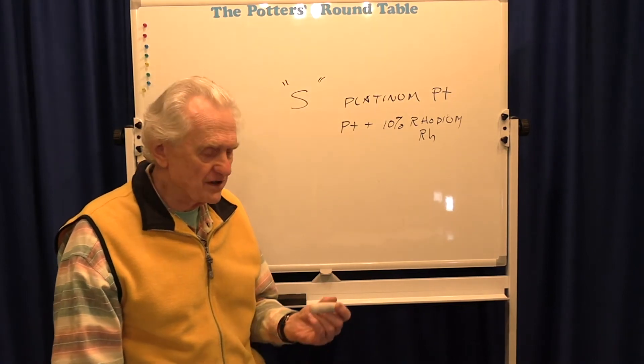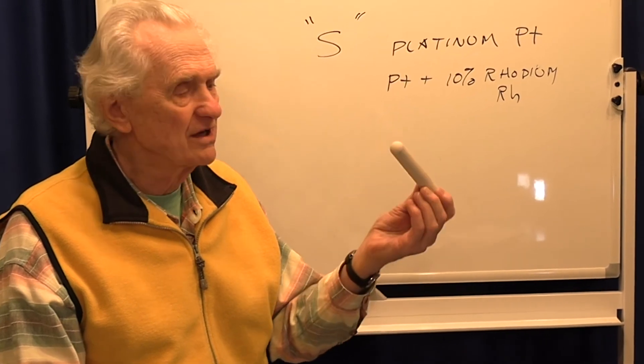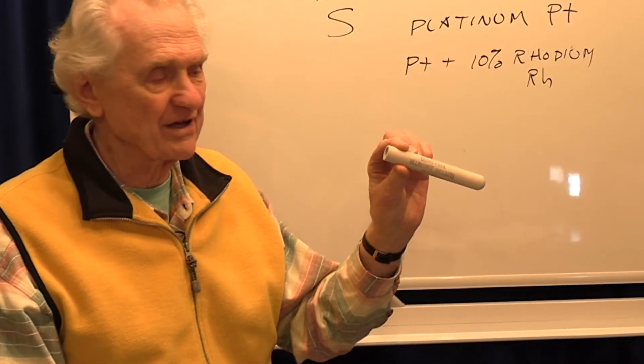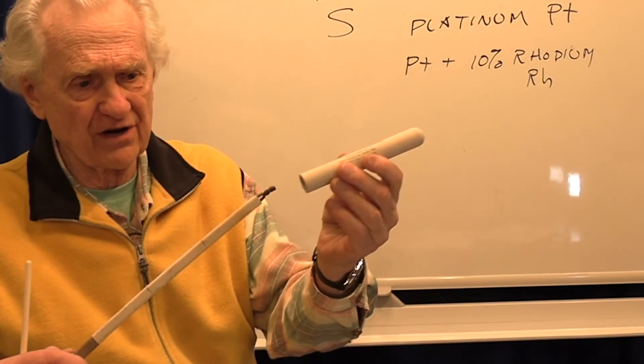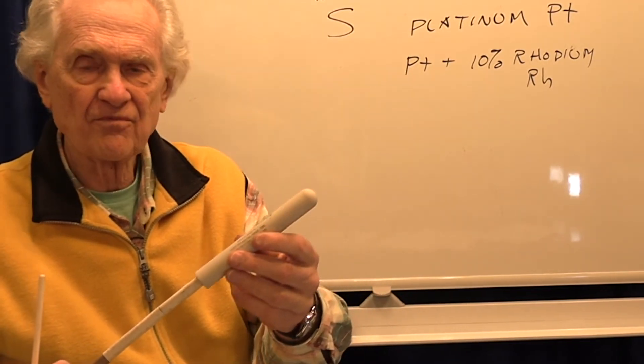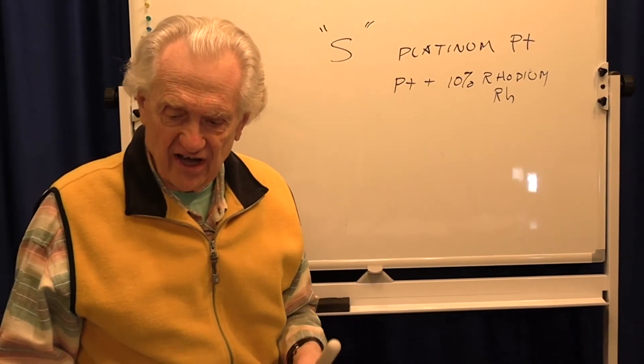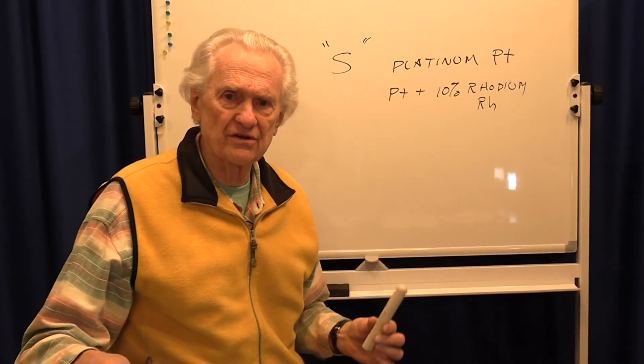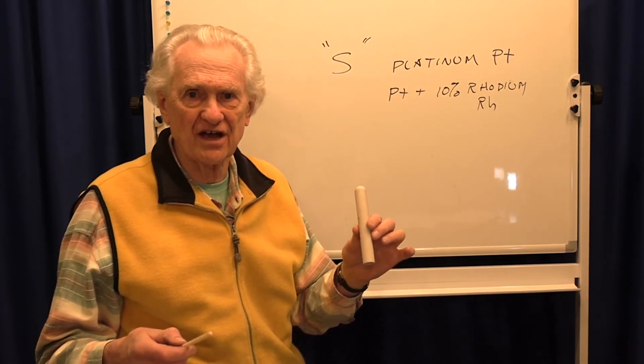The tubes really are two different types. You can have a ceramic tube. This is a large mullite tube from an industrial application. This thermocouple could fit in that tube, and then that projects inside the kiln. Basically that protects the end of the thermocouple from corrosive fumes and also from mechanical abuse in case you actually bumped into it.